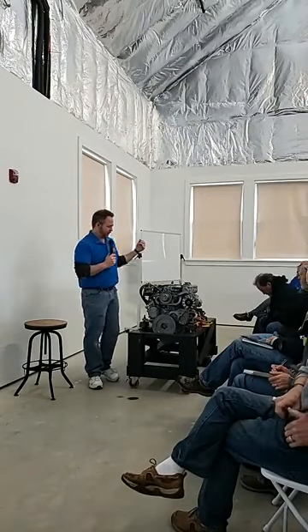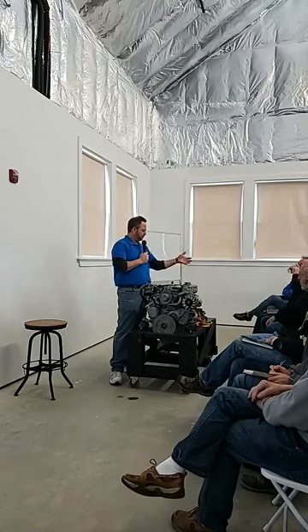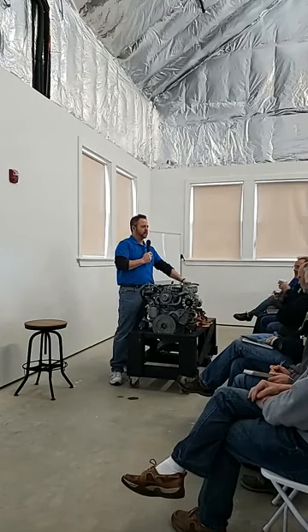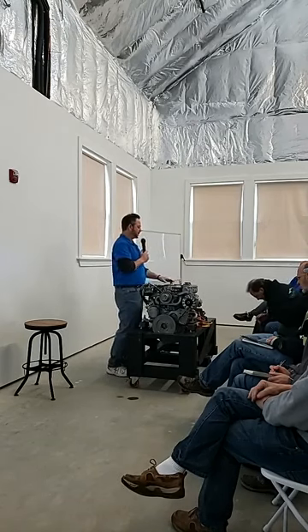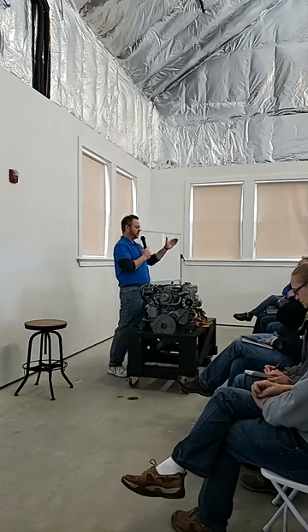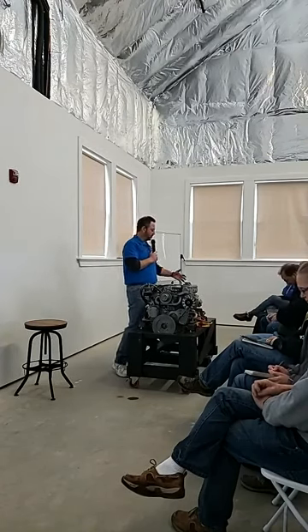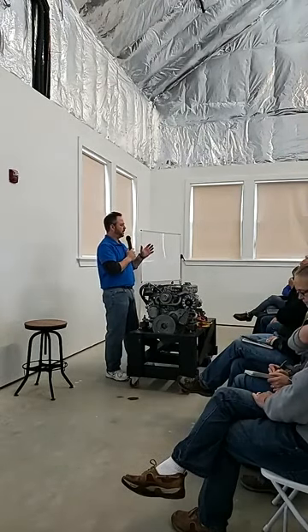All right, so we need good air going in, good air coming out, and so we talked about the exhaust riser having a problem with carbon buildup, but the exhaust hose also, if you have too many 90-degree elbows or 45-degree elbows in your exhaust system, each bend starts adding back pressure. And also, a marine exhaust hose is a 2-ply hose with wire between the 2 layers, and then the layers are glued together.